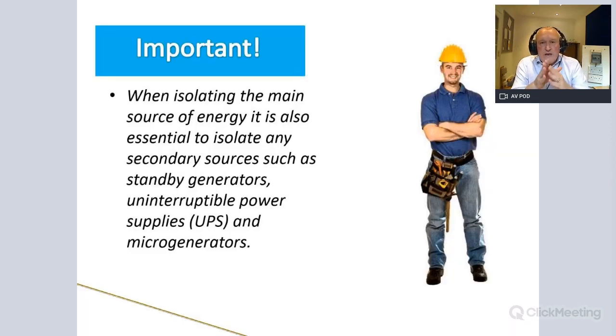As I mentioned earlier, when isolating the supply, ensure there aren't any other known sources of supply, such as a UPS, an uninterruptible power supply. That's basically a machine with batteries in it. You wouldn't really get this in a domestic scenario, but in commercial premises, offices, banks, even on tills in supermarkets. If there's a power cut, the UPS kicks in, so the batteries take over from the power supply and still keep supplying that piece of kit with 230 volts. If a system had a UPS and you didn't know about it, and went straight to work on that till, you'd get an electric shock. So isolate all known sources of supply.